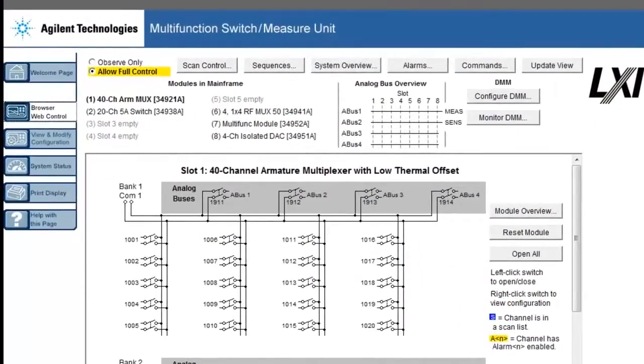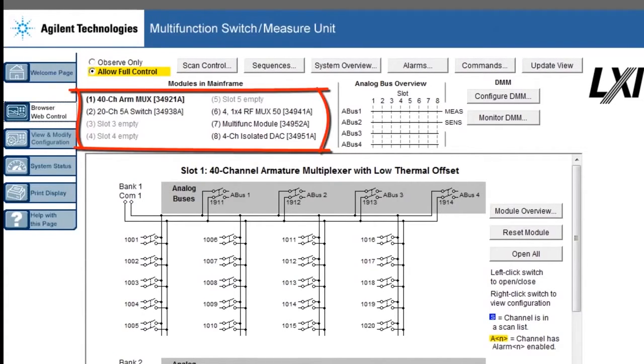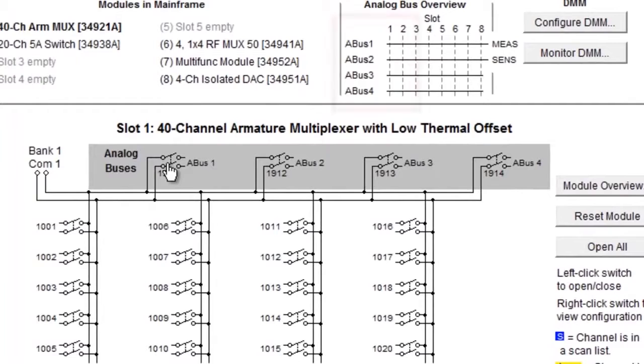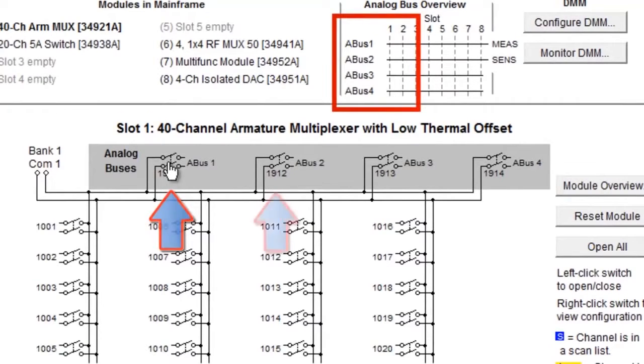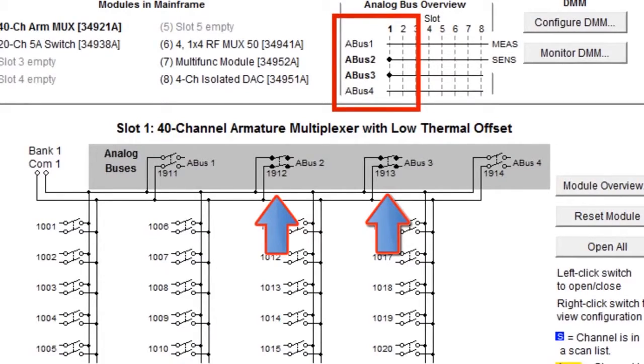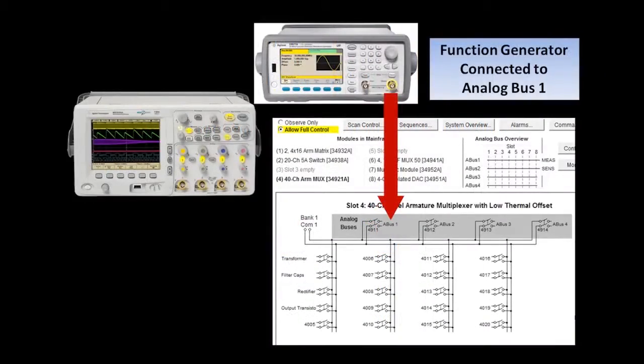So this 34980 comes with a built-in web user interface, which is very useful so that you can see the overall topology of what's happening inside the box. As you can see at the top, there's switches that control each one of the four analog buses. I've used the function generator, it's set up to output a sine wave, and the sine wave has been fed into analog bus 1.